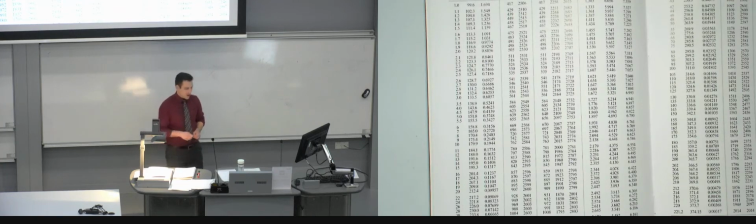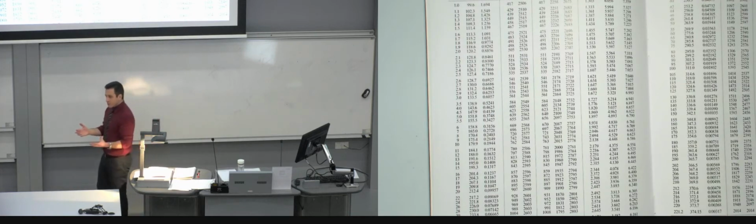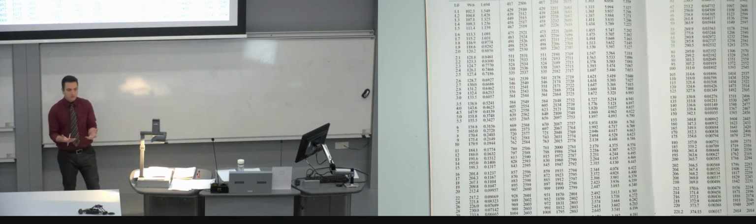This now shows you why in a lot of power plants, for example, let's take nuclear reactors. In a typical UK fleet of advanced gas-cooled reactors, you're looking at about 40 bar. Why do we have to have 40 bar in a reactor, when we clearly know that high pressure is more risky from an engineering point of view, because you've got potential structural damage and the function of the components? But on the positive note, if you raise the pressure in the core of the reactor up to about 40 bar, that means you're going to have steam at a much higher temperature.